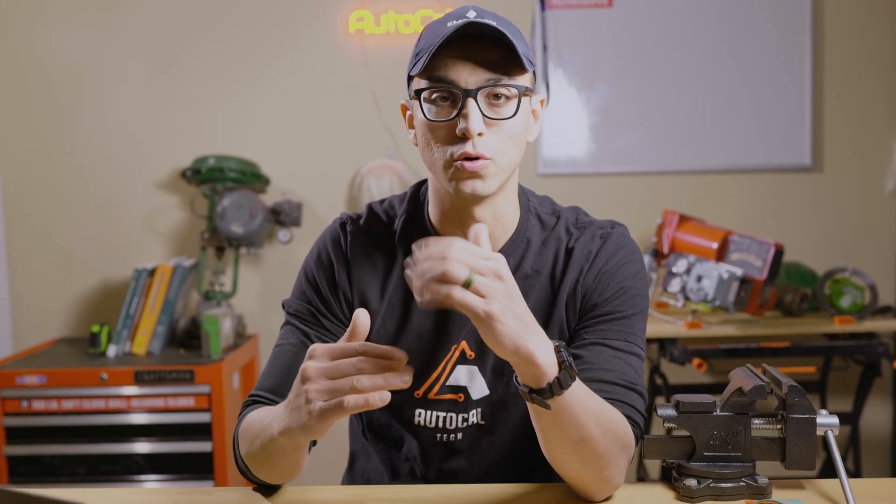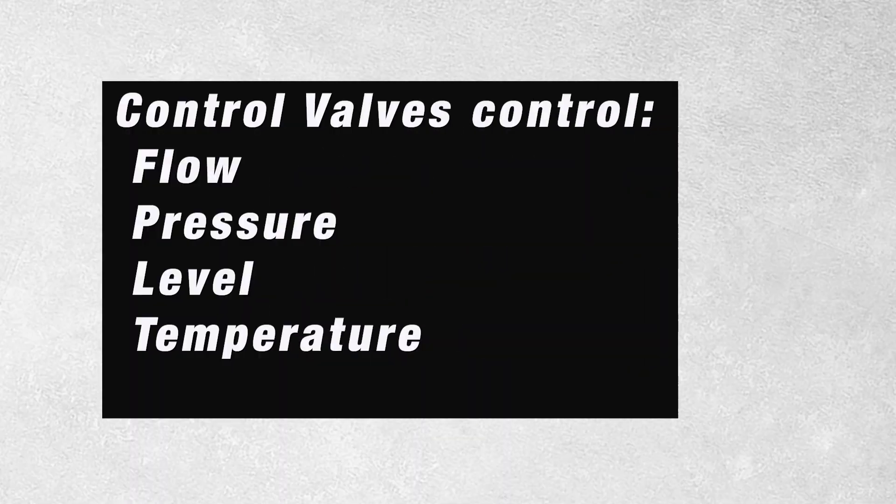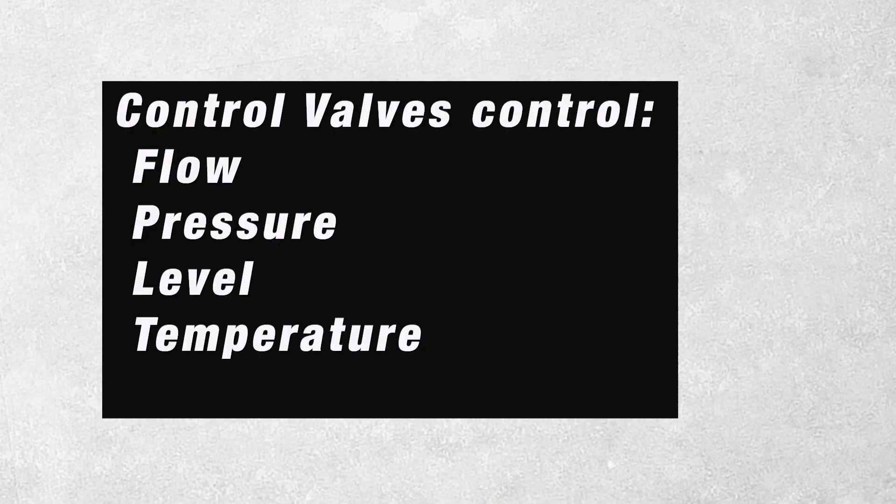The controller calculates what the error is and outputs a signal to the final control element to fix that error. The final control element is usually a control valve — that's how a control valve knows whether to open a little more or close a little more. Right behind me I have a Fisher control valve and on my other side I have a Camflex control valve. One is a rotary and the other is reciprocating, but they both open and close to control flow rate, level in a column or tank, or even temperature.